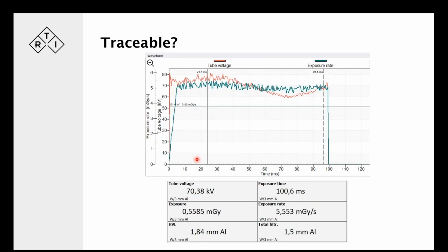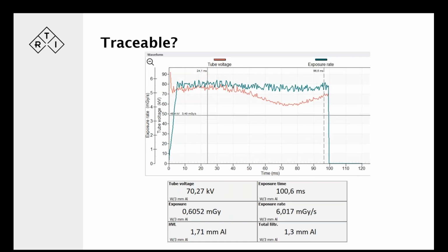Here's another one, 70.38. It oscillates, goes down to something around 60 and up to 80 kV. So it oscillates around there, but still the data that we're showing is 70.38. And last but not least, here we've got another one that also undulates, down to 60 and spikes up to above 90 kV. But in the Excel spreadsheet, what we have here is 70.27 kV.